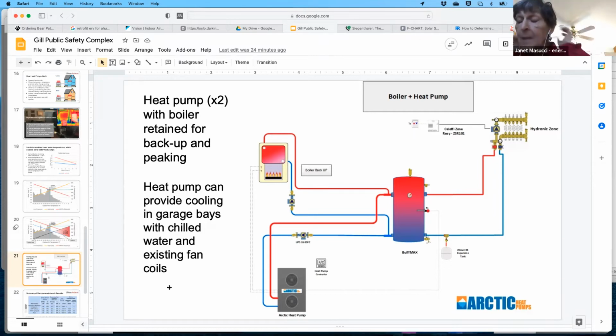I'm dyslexic. Basically, you're saying the highway department will get cooled in that building, that room there. Yes, any place that is an office and has fin tube or baseboard distribution, which can't do cooling, you'd want to use an air-to-air heat pump so those spaces can get cooling and heating independently from the temperatures required for the garages. Okay, thank you.